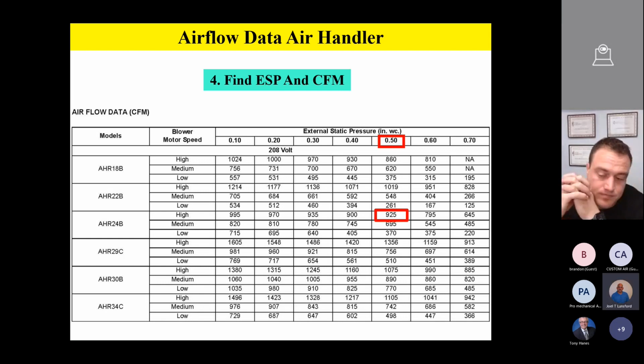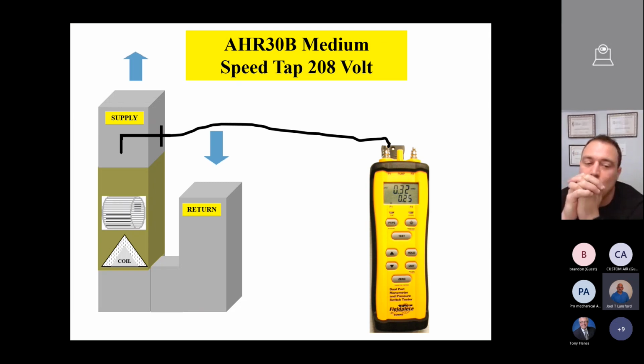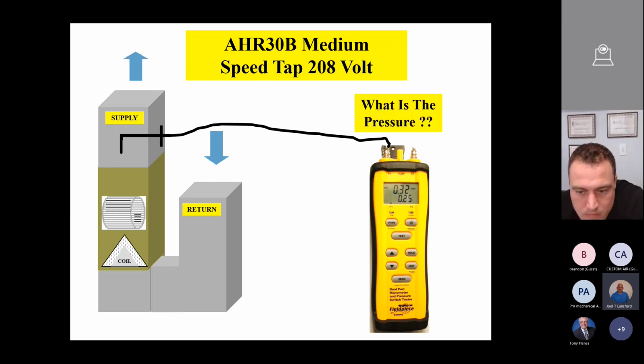So as we're referring to those charts, everyone should have some little charts that we sent out earlier a few weeks back. So let's say, for instance, we have an AHR 30B. It's on a medium speed tap, and we're looking at the 208 volt portion of that chart. So as we take a look at our digital manometer and our static pressure probe, the AHR 30B on medium speed tap, we correlate that on the chart, 208 volt section on the airflow chart. And we see our first reading is a 0.32. So the supply static pressure is a 0.32. And so I either write that down or I just remember it.